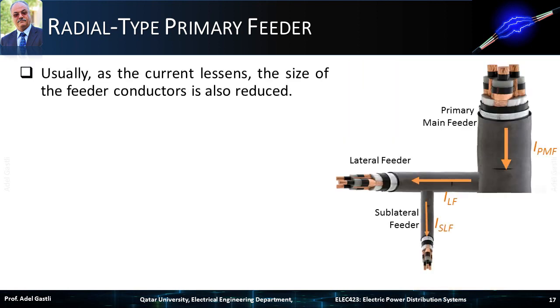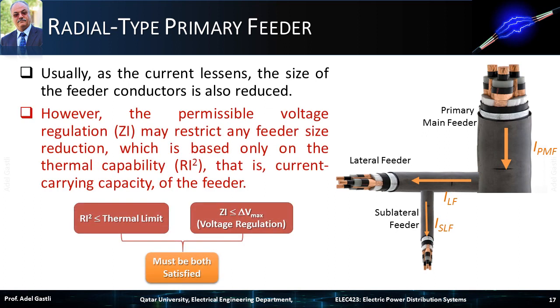Usually, as the current lessens, the size of the feeder conductors is also reduced. However, the permissible voltage regulation — that is, conductor impedance times current — may restrict any feeder size reduction which is based only on the thermal capability (RI²), that is, the current carrying capacity of the feeder. So both cable thermal limit and voltage regulation must be satisfied when sizing and selecting the proper feeder cables.